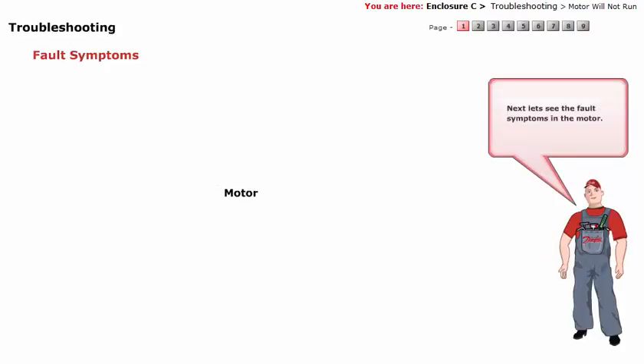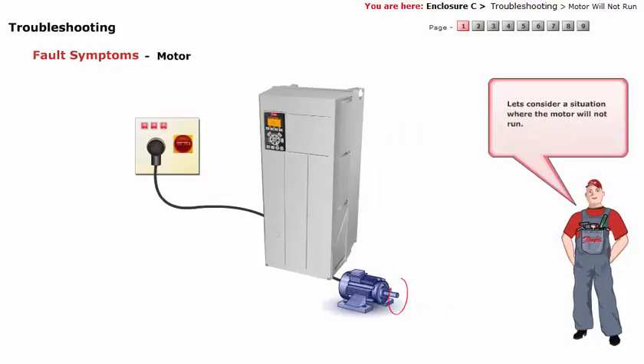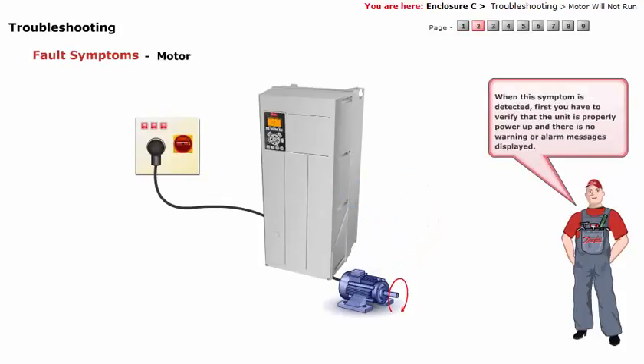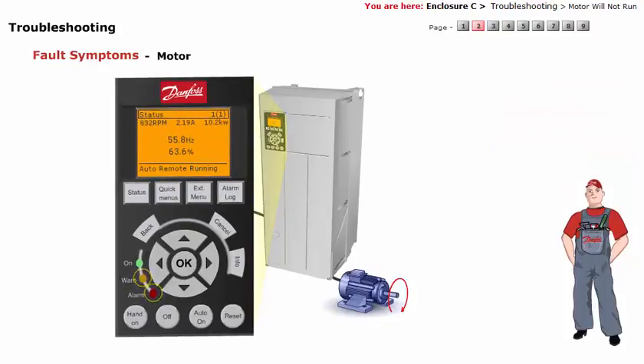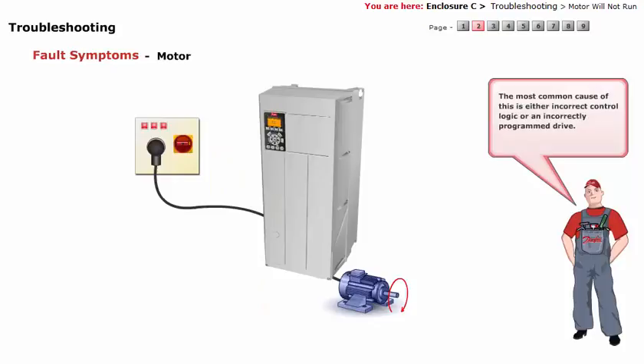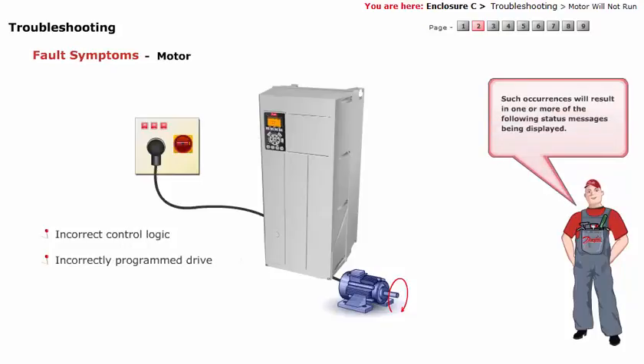Next, let's see the fault symptoms in the motor. Let's consider a situation where the motor will not run. When the symptom is detected, first verify that the unit is properly powered up and there are no warning or alarm messages displayed. The most common cause is either incorrect control logic or an incorrectly programmed drive. Such occurrences will result in one or more of the following status messages being displayed.